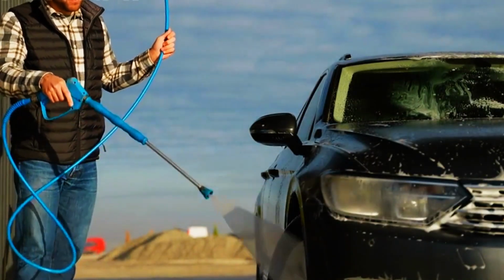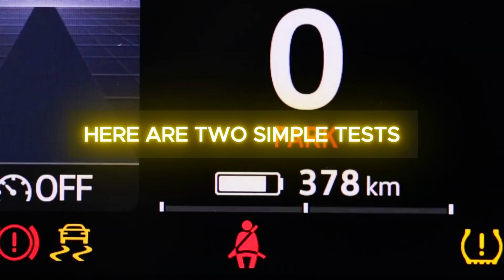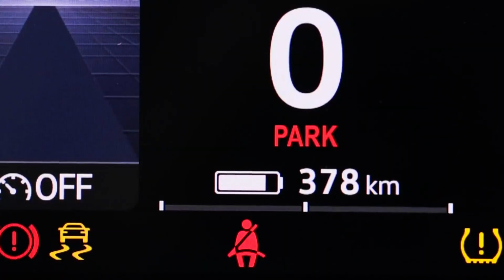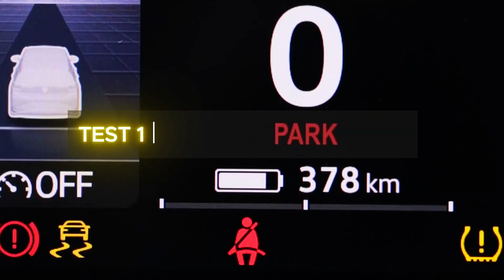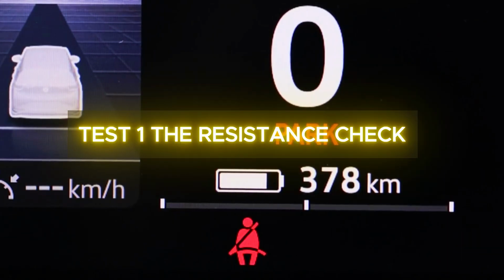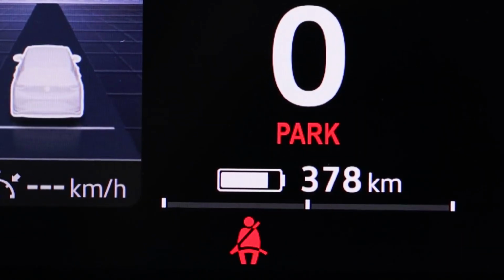How to quickly test your ground connection. Think you might have a bad ground? Here are 2 simple tests you can perform with a basic tool called a multimeter. Test 1: the resistance check. Turn the dial on your multimeter to the resistance setting, marked with the ohm symbol, omega. You'll want to use the lowest possible range.